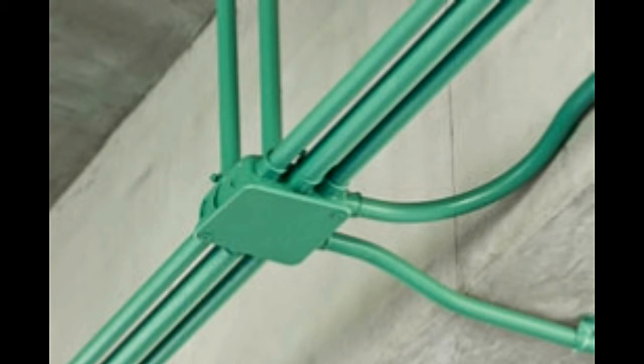The minimum size raceway that can be installed is half an inch. To install underground electrical conduit, you need to dig the ground at least 18 inches deep.